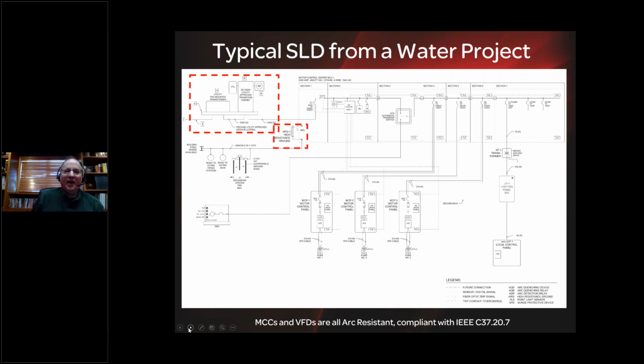We do highly recommend high resistance grounding, whether you have an arc quencher or not, because although high resistance grounding does not reduce arc flash incident energy, it reduces the risk, the probability of an arc flash event occurring by at least 95%, according to IEEE. And what that means in real world terms in this arc quencher application is that the odds, the risk that the arc quencher will ever need to operate, in fact, is reduced by 95%.